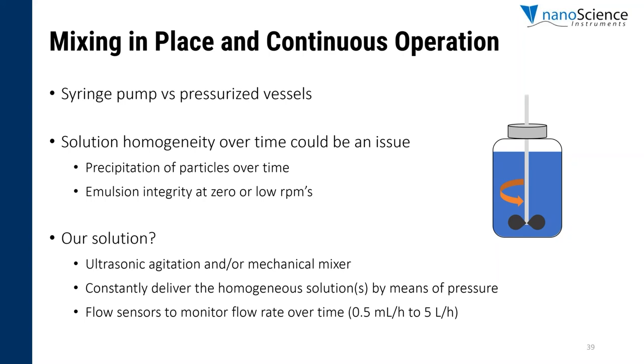Our solution is pressurized vessels that can hold more than 3 liters of solution. We can use ultrasonic agitation or mechanical mixing for the main solution to keep its integrity. This way we can maintain emulsion integrity over time and keep particles suspended in solution for better homogeneity, if that's needed for your application.